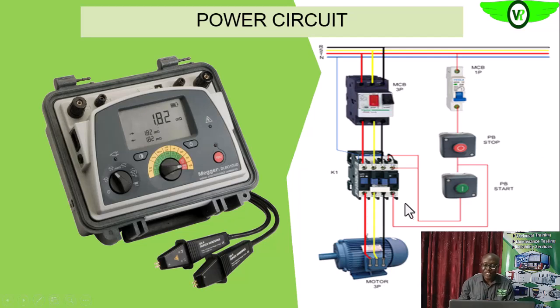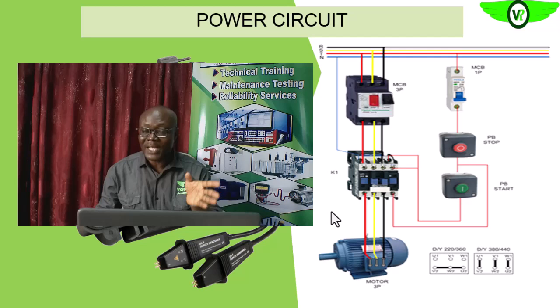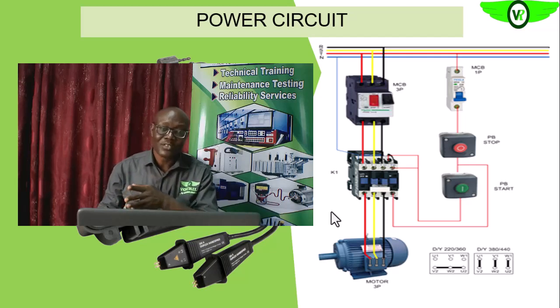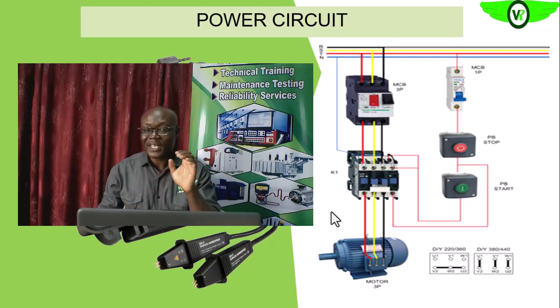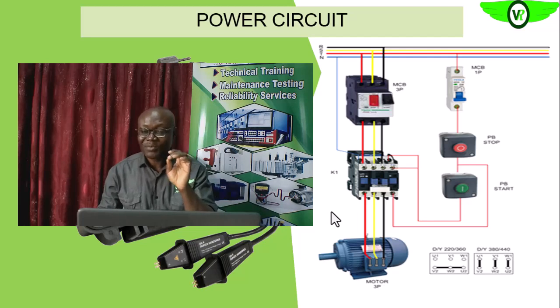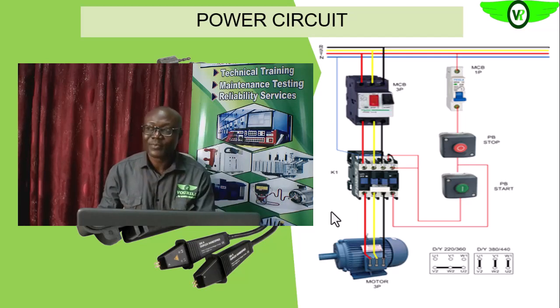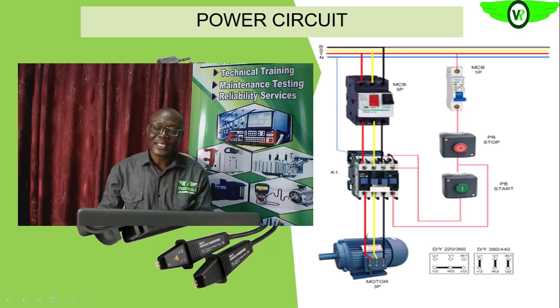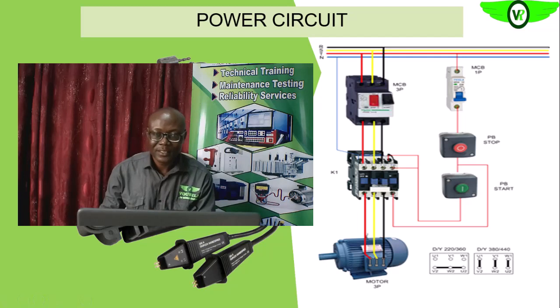So which means that whichever point, if it is line 1, line 2, we take, line 2, line 3 we take, or line 2, line 1, line 3, and line 2, line 3 we take, you see that since we are looking at the same length of cable, the same resistances, that is the same winding, that two winding in each readings, okay, we expect that the resistance reading should be the same. Are we getting it? So again, we look at the unbalance here.